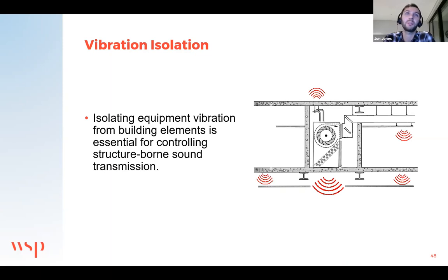I think vibration is important acoustically, and once any sort of building services equipment vibrates and that energy gets into the structure of a building, it can be very hard to mitigate and predict, and can be very annoying as the sound re-radiates elsewhere in the building as re-radiated noise from the equipment. So as a rule of thumb, any equipment should be fitted with some sort of anti-vibration treatment, particularly if it's in a sensitive area.